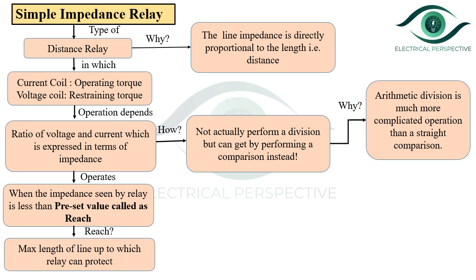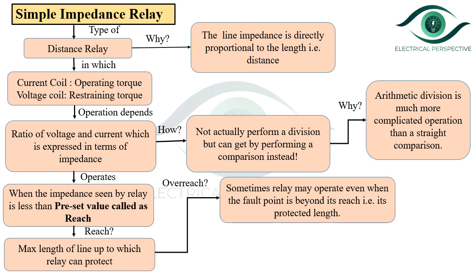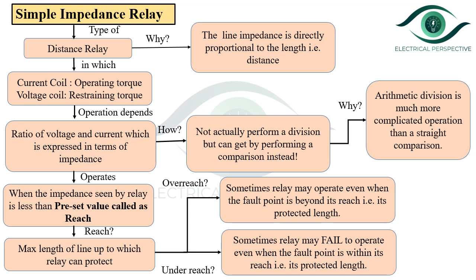What is reach? It is the maximum length of line up to which the relay can protect. There are two terminologies: overreach, meaning that sometimes the relay may operate even when the fault point is beyond its reach, that is beyond its protected length; and underreach, meaning that sometimes the relay may fail to operate even when the fault point is within its reach, that is within its protected length.